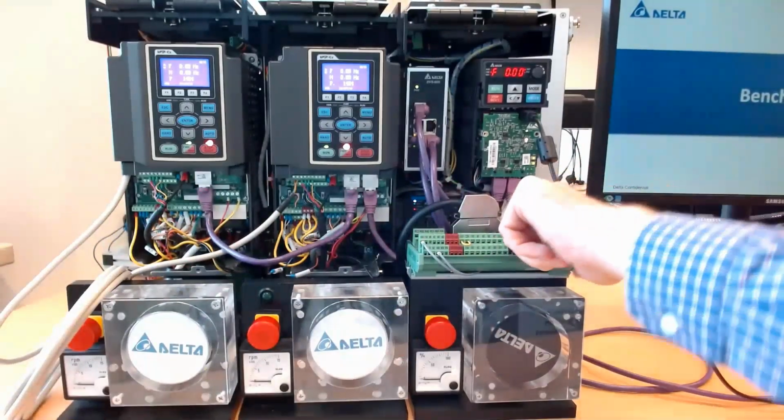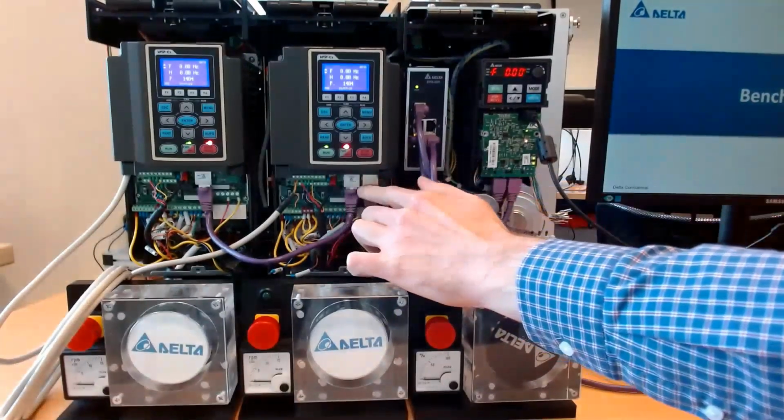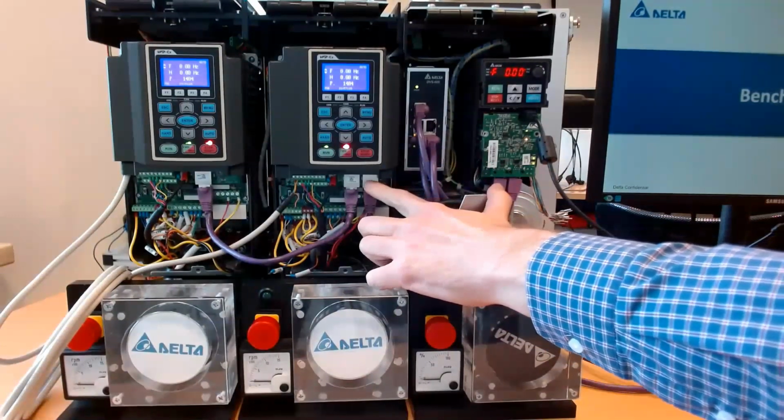I'm also connecting my laptop to this switch, which is connected to an AS200 drive, which is somewhere behind. And then from the switch, I'm also going into a daisy chain connection from the switch to the dual port Ethernet IP card. And from this Ethernet IP card, I'm then going into this dual port Ethernet IP card on this slave, on this follower C2000 drive. And then from it, I'm going into a single port Ethernet IP card, which is connected to another C2000 drive.